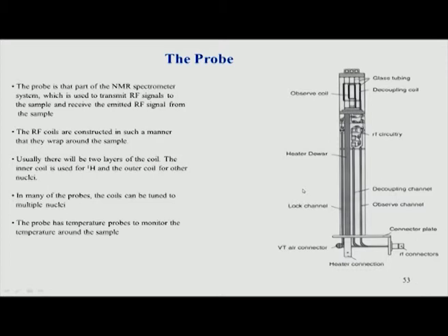So, again this is more detail about a probe, how it looks. The main point here is that these coils actually wrap around the sample. The sample is very tightly wrapped by the coil, and that is called the filling factor, which is a more technical detail. Essentially the sample is very close to the coil, and whatever signal is emitted from the sample is immediately taken up by the coil in the vicinity.